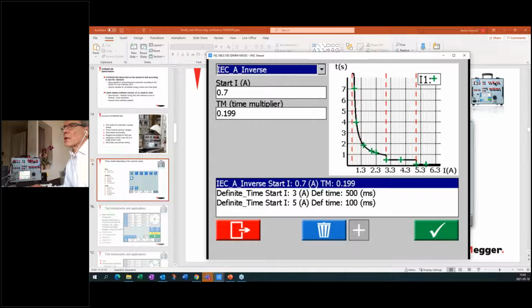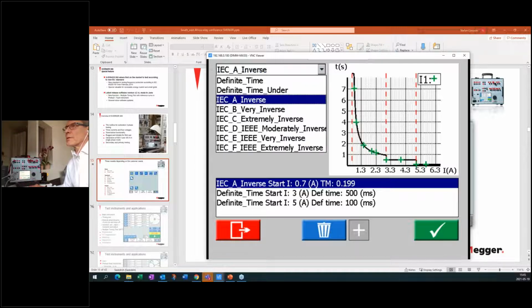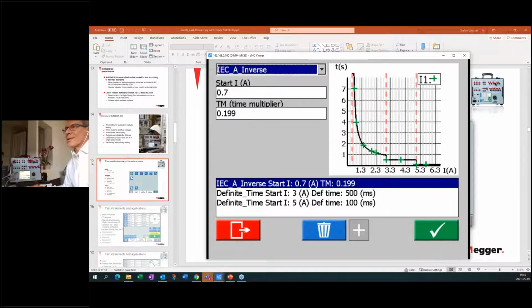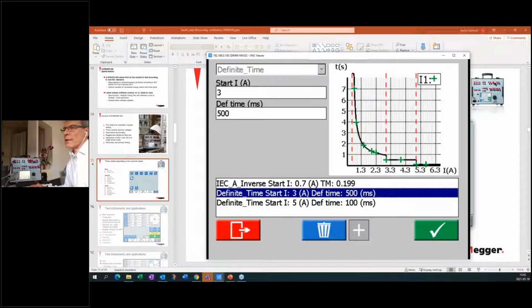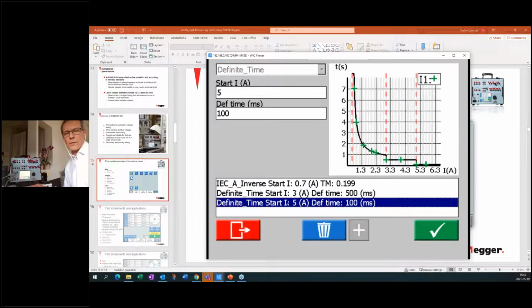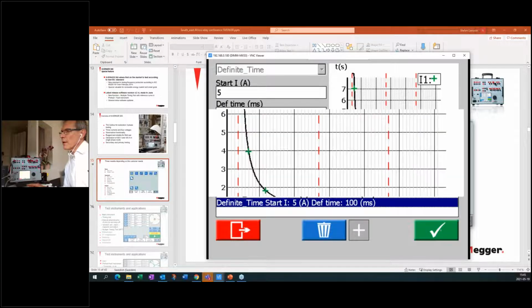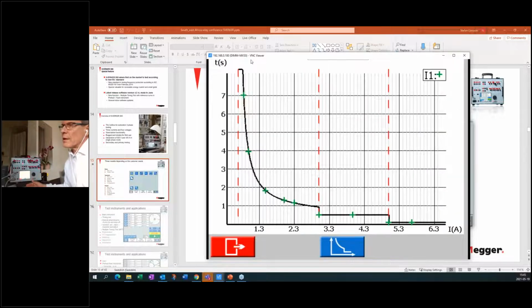So I can change, but now I have already set the settings which are in this protection. But it's possible to do the settings, whatever is set in the protection. So I have the first threshold, and the next threshold is definite time, and then we have the third threshold, it's also definite time. Then I can see on the big screen the test together with the reference graph, and visibly I can see, okay, this is looking good. And then I'm fine with this.